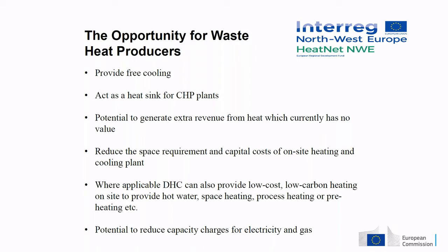There's potential to generate extra revenue from heat which currently has no value and is sent to drain or released into the atmosphere. You can reduce space requirements so there's less need for plant on site - it's all off site. You're essentially replacing your heating and cooling plant with a heat exchanger. There's also potential to provide heat to the site for things like preheating or low-grade process heating, and to reduce capacity charges for electricity and gas. If equipment that previously consumed electricity or gas for cooling and heating can now be provided through the district heating network, there's a reduction in the electrical and gas capacity required on site, and so a monetary saving.